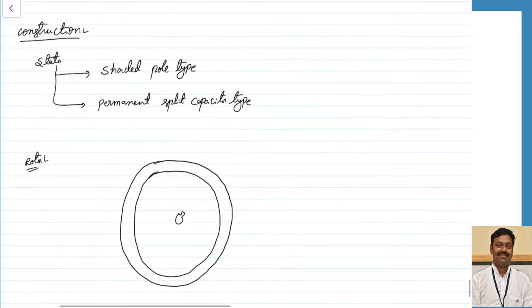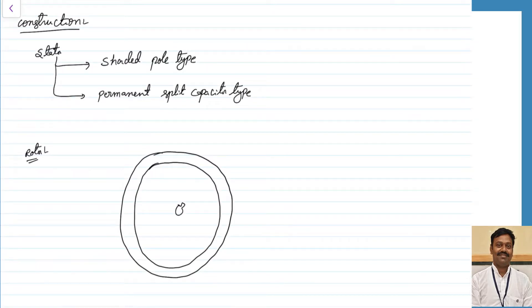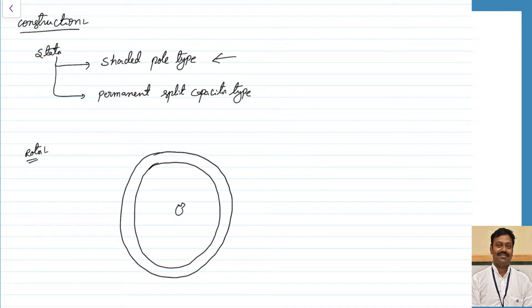Now let us see the construction. The stator can be similar to that of a single phase machine or a three phase machine. Either you can go for three phase balanced winding, which produces a three phase rotating magnetic field — then it is called a three phase hysteresis motor. If you want to operate on single phase, as is the case in most applications, we can go for either shaded pole type or permanent split capacitor type.